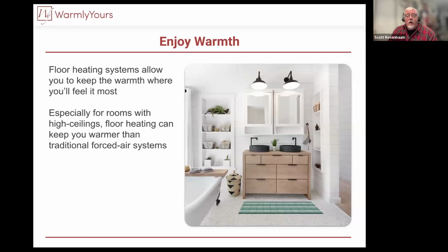Now take a look at the drawing or the picture here. You can actually see this is a tub up on legs. We would not put the heat under that tub because there's a pretty good chance if you look at that leg, it's probably bolted. There's a possibility that it's bolted to the floor, and you don't run bolts through electric floor heating. That's a bad combination because running a bolt through the electric wire can damage it. So we would stay out from under that tub because it's a permanent fixture. It's sitting there on legs, but you're never going to move it.